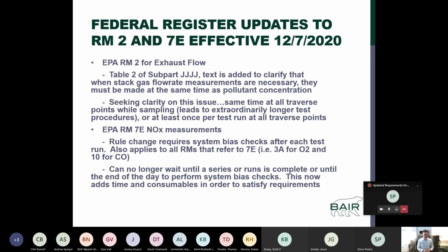Well, method 7E has had language up until now, or until December 7th of this year, that says you can run the risk of holding off to do your post-run system bias check until the end of the test series, or the completion of an engine, or if you're doing multiple engines in one day, you can wait until the end of the day. You can risk doing that post-run bias check on your system, but if you fail it at the end of the day, it invalidates all runs up until your last system bias check.